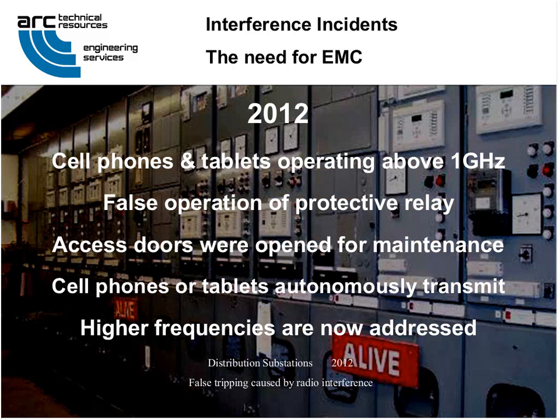How far was that camera from the site? Where was the camera? In the guy's hands. He was on site. The photographer was an employee. They opened up the back of the panels, which you shouldn't do, and then they took the picture, and then the pump controller went offline and did not set off an alarm, and it starved the cores of cooling water. They went into an organized shutdown. There was no release. However, the plant failed. It was taken offline by a consumer camera. Scary, huh?